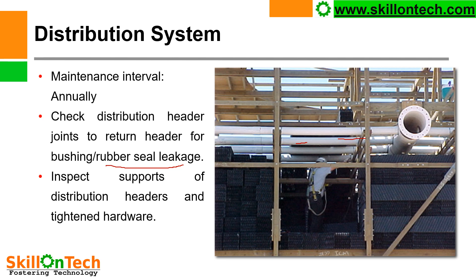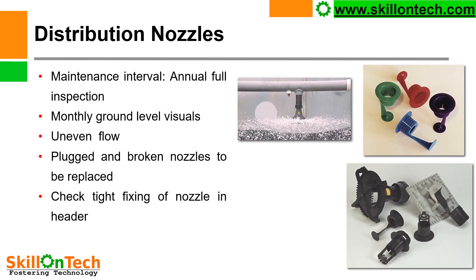The supports of distribution headers shall also be inspected annually or whenever an opportune shutdown comes, to verify the intactness of the headers and supports. Here you can see the distribution nozzles. Various types of distribution nozzles are available, and hole sizes come in 8mm, 10mm, 12mm, and various other sizes, as per the requirement to maintain pressure in the header.